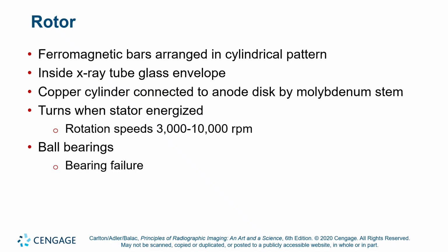The ball bearings, once they start glowing red and orange, they start to warp from spheroids into ellipsoids, and that's considered bearing failure. Your rotary axle will start to wobble, and your entire anode wheel will start to wobble. When that happens, your focal spot size gets radically large with anode wobble, and so you've ruined your X-ray tube at that point. And so part of the heat capacity and allowing the anode to cool off is to prevent rotor bearing warp. We also want to prevent the pitting to the anode wheel itself, but rotor bearing warp is far more common a concern.